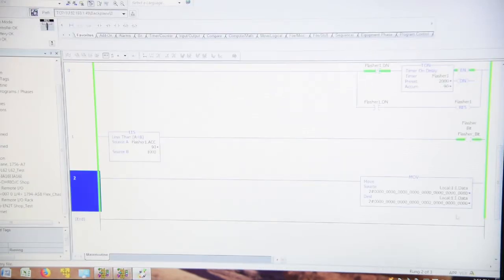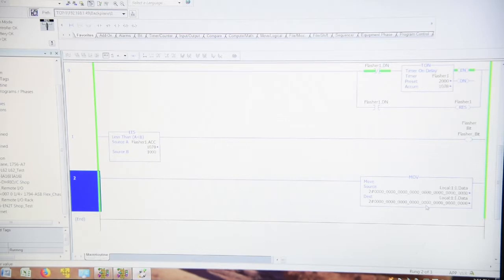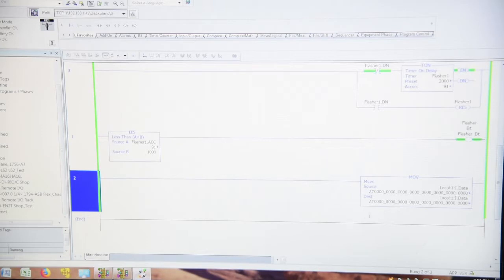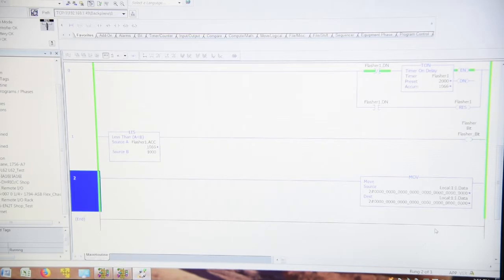We go to our Control Logix. And again, in the Control Logix, you're looking at a 32-bit word. So in this case, we're only looking at the 16 that are coming in. The other 16, if we had a 32-bit card in there, would be flashing on and off. So you can look at them, you can see that all the bits are on. So we know that all of these cards are good.